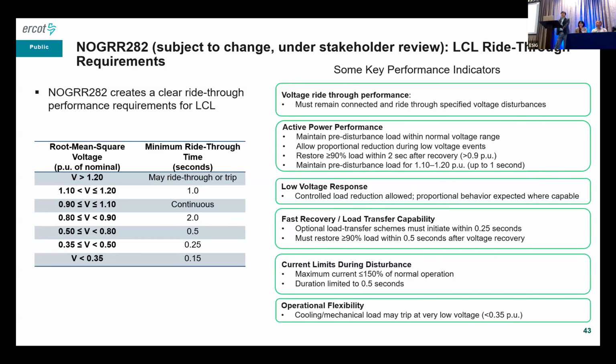I'm not going to talk about the details of NOGRR 282, but here's the summary of voltage ride-through requirements outlined in it. On the left, you see voltage bands and corresponding minimum ride-through durations. So they have to ride through the fault within those requirements. And on the right, we have some key performance indicators. One of the things I can say is they have to continue to consume power during the low voltage dip and also high voltage conditions. And once the voltage is recovered after the fault is cleared, they have to come back to the grid within 2 seconds. Okay, so again, this NOGRR 282 is available on the public website, so you can go ahead and take a look at it for more detail.